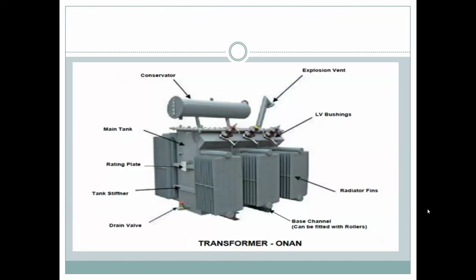Next. This is a sketch of a transformer, how it looks. These are radiators, the cooling radiators. This is the conservator where the oil is filled up, and this is the explosion vent. If the pressure goes up in the tank, the oil comes through.